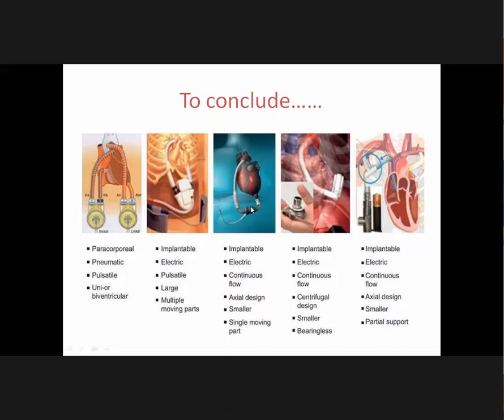This is HeartMate 2, and this is further replaced by the HeartMate 3, which are implantable electric and also continuous flow but with centrifugal design, which are smaller and lack bearings. These are further being replaced by even smaller devices such as HVAD, which are implantable electric continuous flow systems with axial design, which are smaller still, with partial support only.